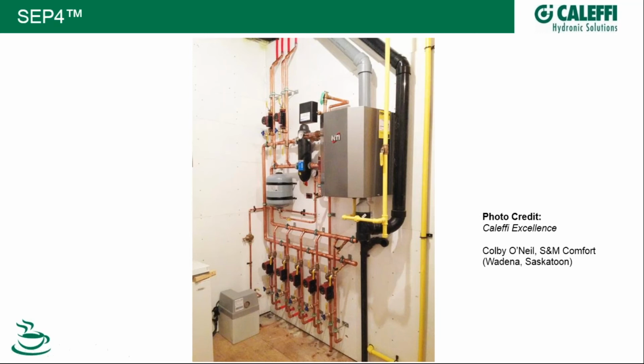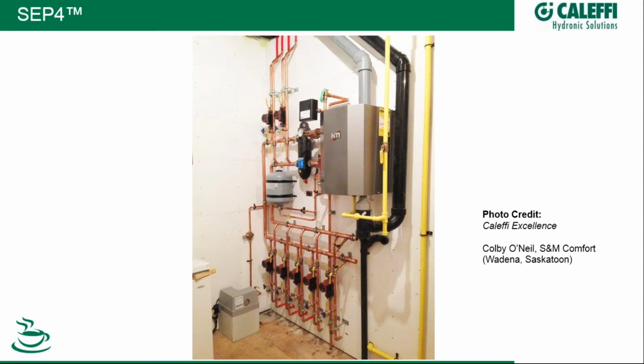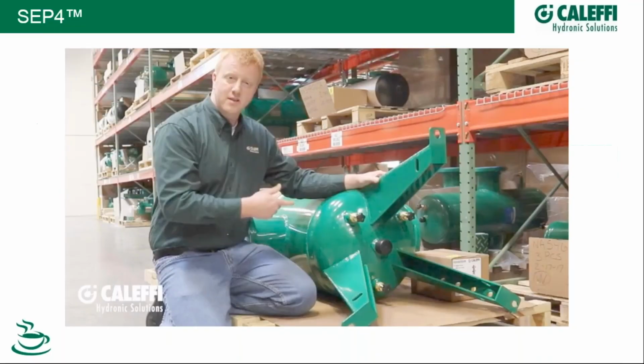Glycol is an oxygen scavenger, and to the extent that oxygen gets into a system, as glycol absorbs oxygen, as we've shown in other webinars, you will start to see the pH begin to drop. Basically, the glycol can become acidic. So to the extent that air gets into any type of glycol system, you want to get it out, like Mr. O'Neill did right here with the SEP4. Now jumping to our commercial size SEP4, this is Cody, it's a screen capture.